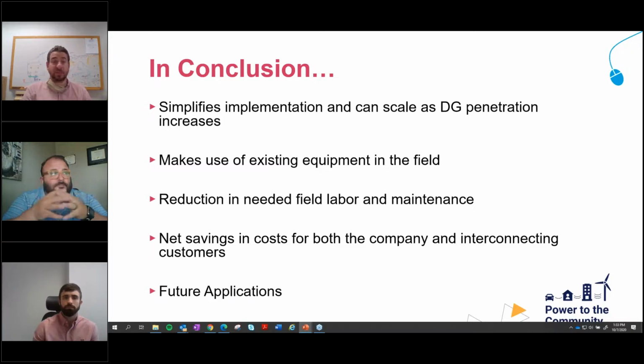So then just some other things we're doing - Ryan and I are playing around with this in other ways with some DER sites. We have some DER sites that are on automatic load transfer schemes, and the sites are only supposed to operate on the normal source. If they get swapped over to the alternate source, they shouldn't be online. So we're going to use the same if-then logic, monitoring the status of the normal source - if they get swapped over, we trip them offline.